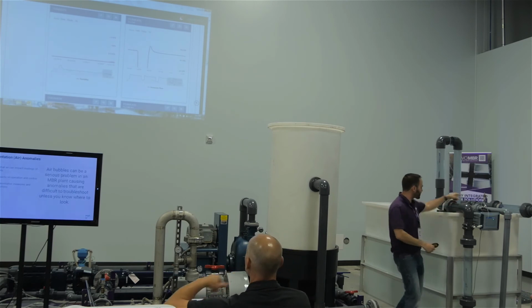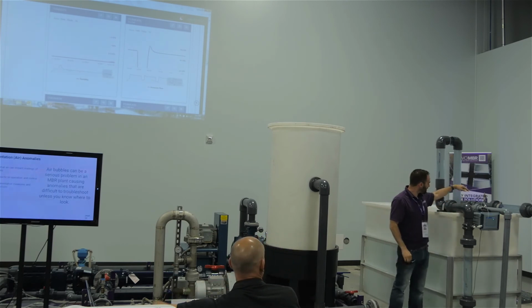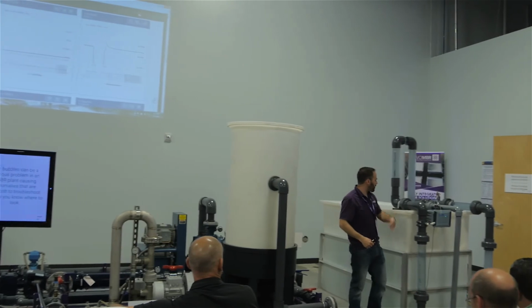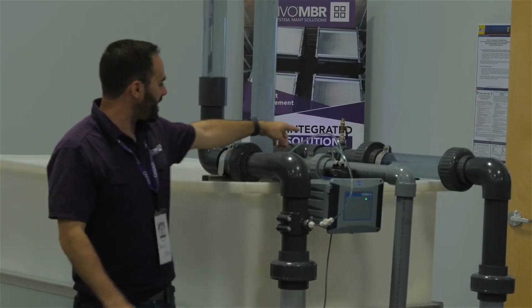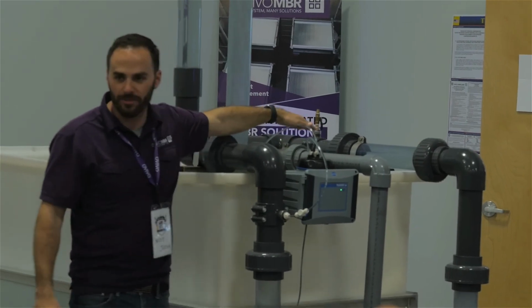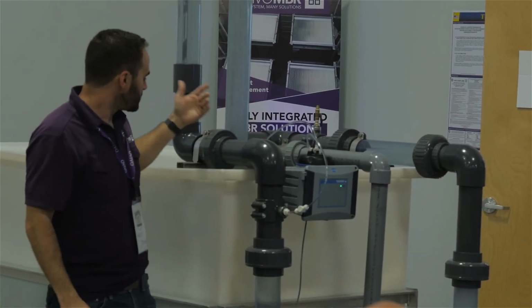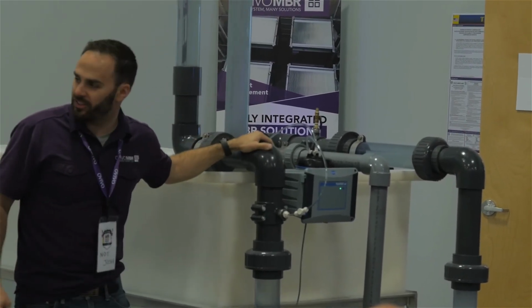The pump's still running, full suction on the piping. The water is flowing that direction, but we're bringing air in through this hole. So again, we didn't properly glue these joints. There are joints everywhere along the pipe.